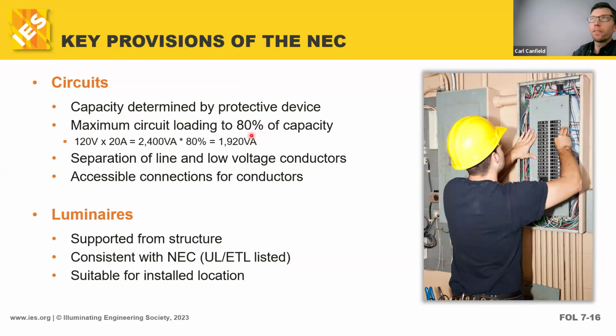We can load that circuit up to 80% of the total capacity. So 120 volts times 20 amps, which is the rating of the circuit breaker, equals 2,400 volt amperes or watts. VA, volt amps, and watts are roughly the same thing. They're not exactly the same thing, but we're not going to worry about that. It's a whole power factor thing. John, I'm sure you are very familiar with that, outside the scope of this. But for this argument's sake, here's our 100% capacity of a single 20 amp, 120 volt circuit. We would derate by that 80% safety factor. And so we could load up that circuit to 1,920 watts worth of load. It could be light bulbs, it could be receptacles, what have you.